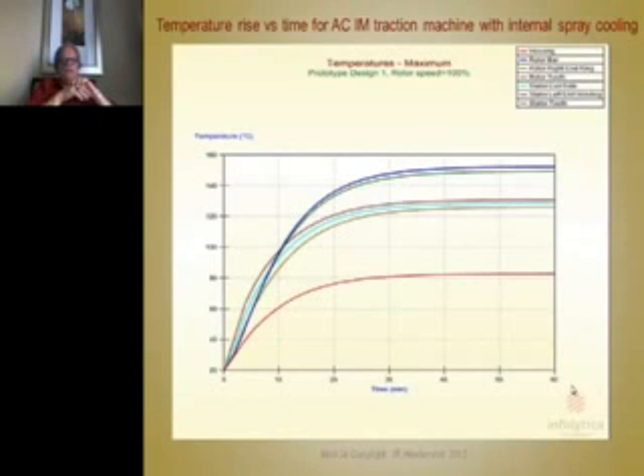This is a typical plot that you would get. This happens to be an Infolytica 3D finite element thermal model for a traction motor for a vehicle, and it's a big one. It's 100 kilowatt machine, and it has internal spray cooling on the rotor and the stator. Has a bunch of spray nozzles that have been modeled, and you see here the temperature rise over time. This is the type of thing you want to study. First of all, it's got to level out. It's got to terminate. Can't keep rising, or you don't have enough cooling.